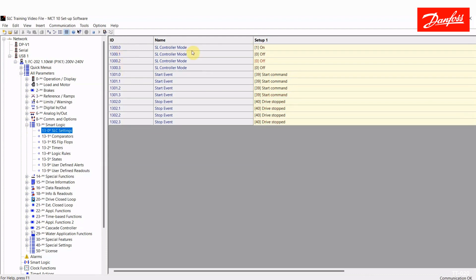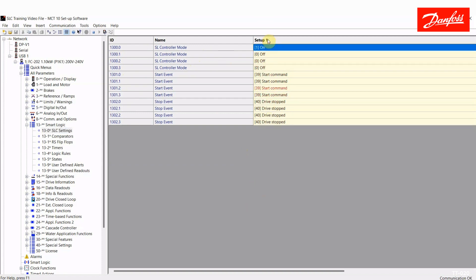That would be for controller 1, 2, 3, and 4. This parameter here happens to be the controller mode. It can be either turned on or off. And then also you have the start and stop event for each of the four controllers. Now by default, this is all off here, and the SmartLogic controller mode does not have to be set to on unless you intend to execute a repeatable sequence.